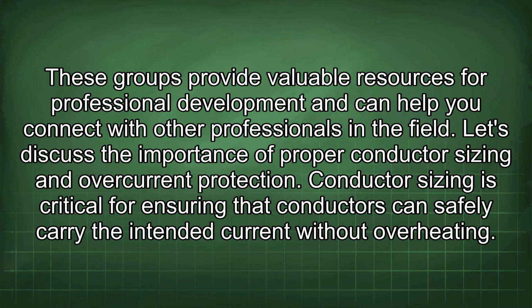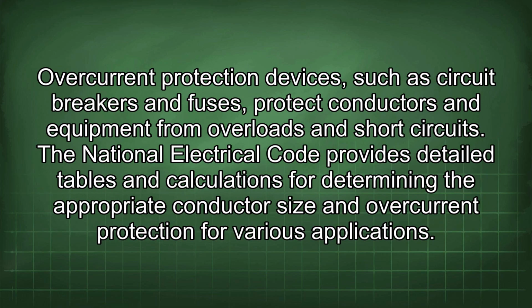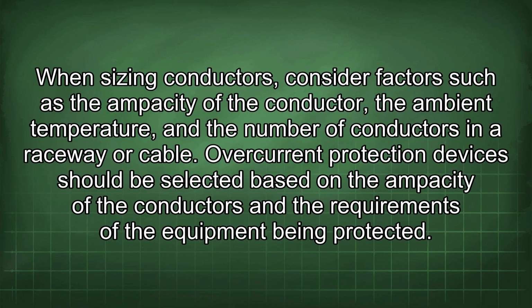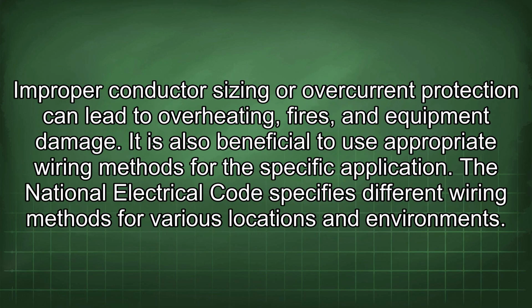Let's discuss the importance of proper conductor sizing and overcurrent protection. Conductor sizing is critical for ensuring that conductors can safely carry the intended current without overheating. Overcurrent protection devices, such as circuit breakers and fuses, protect conductors and equipment from overloads and short circuits. The National Electrical Code provides detailed tables and calculations for determining the appropriate conductor size and overcurrent protection for various applications. When sizing conductors, consider factors such as the ampacity of the conductor, the ambient temperature, and the number of conductors in a raceway or cable. Overcurrent protection devices should be selected based on the ampacity of the conductors and the requirements of the equipment being protected. Improper conductor sizing or overcurrent protection can lead to overheating, fires, and equipment damage.